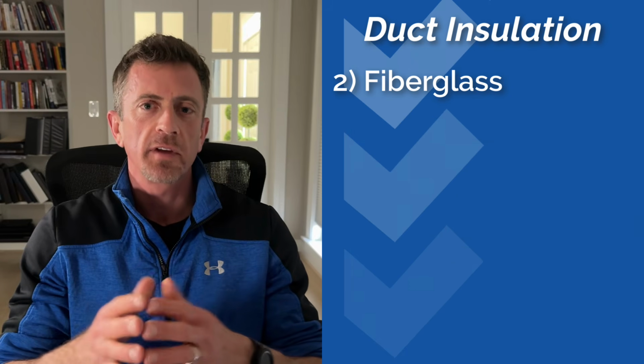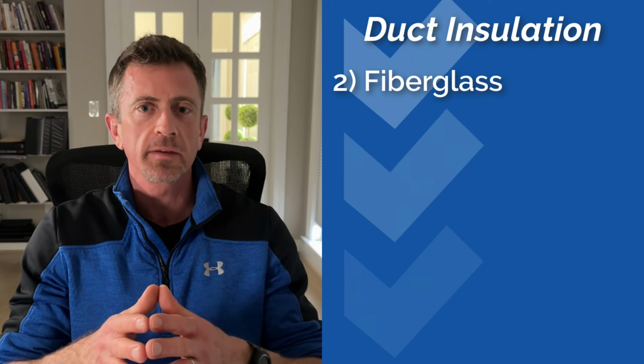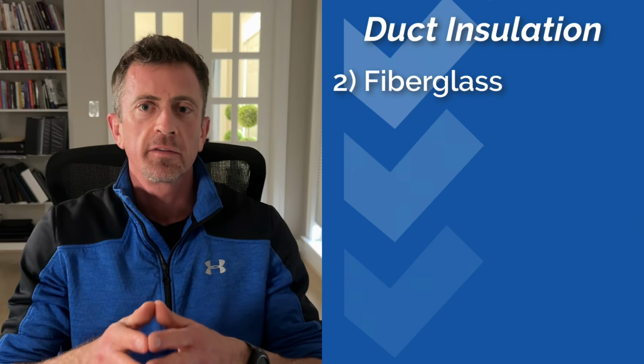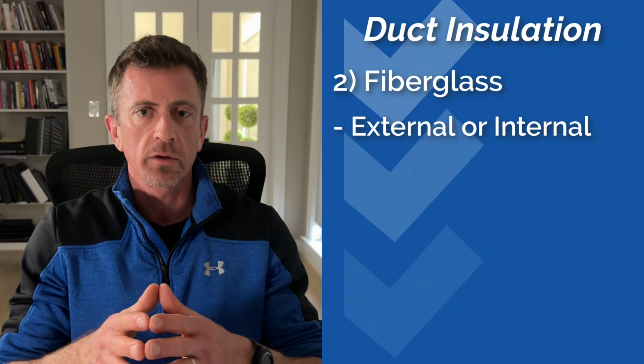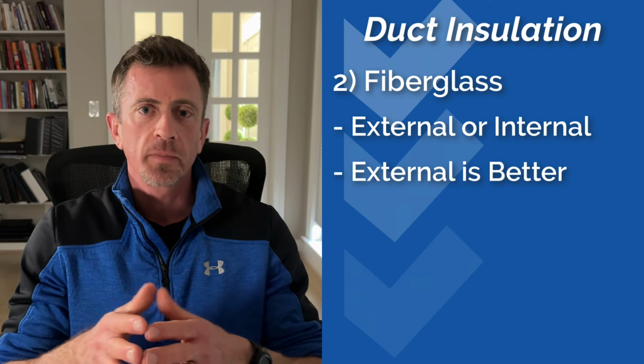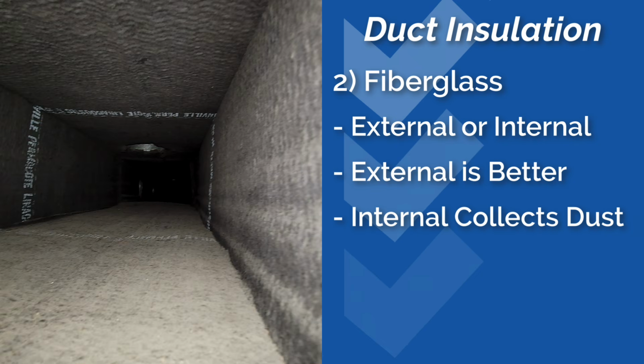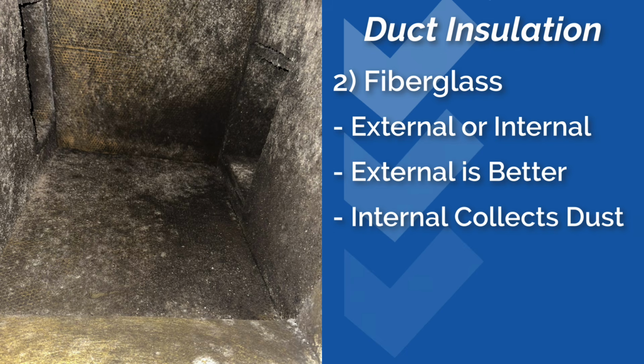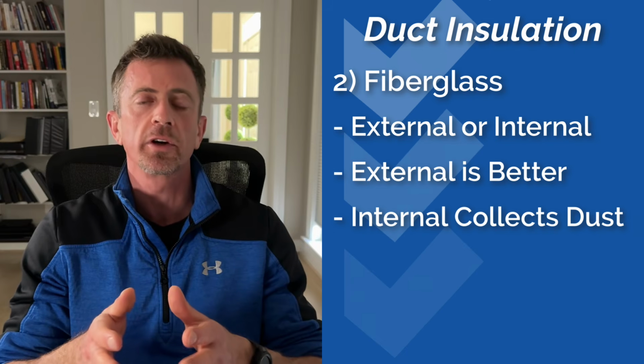The second insulation type is much more common, and it's just fiberglass duct insulation. Fiberglass can be either external or internal, but external is much better. Internal insulation can collect dust, and if the air is humid inside, it can become a breeding ground for mold, mildew, and fungal growth inside your ductwork, and that is horrible for your indoor air quality.